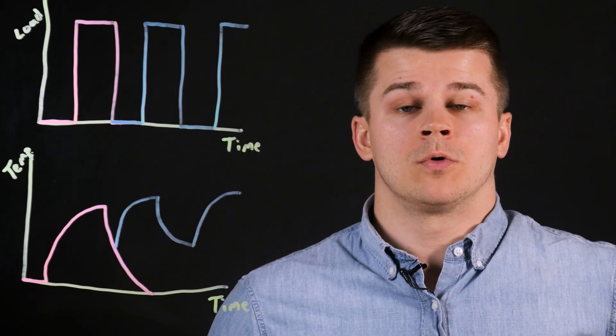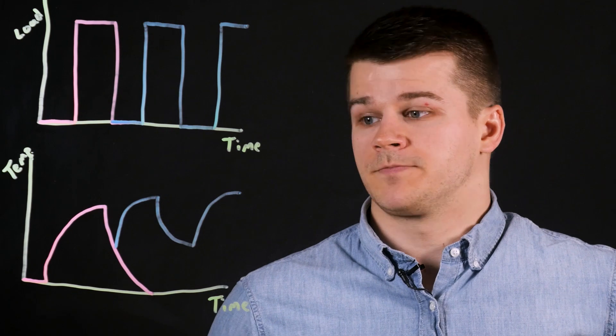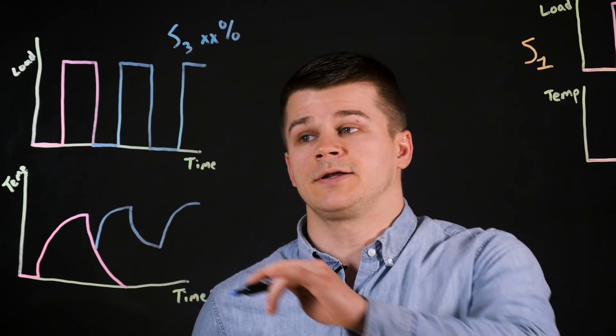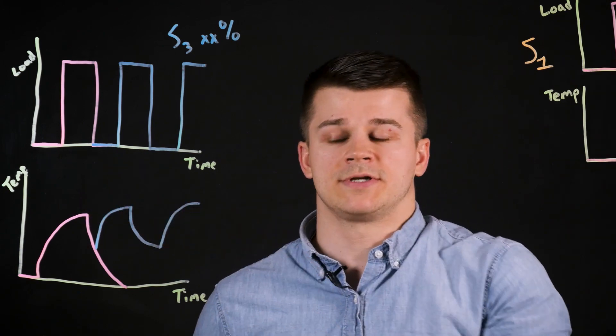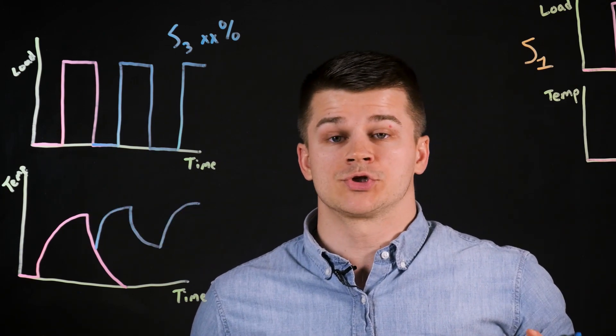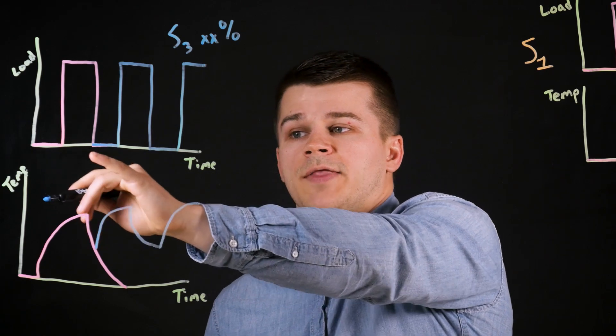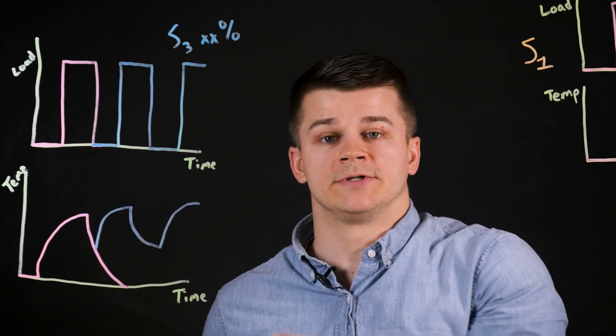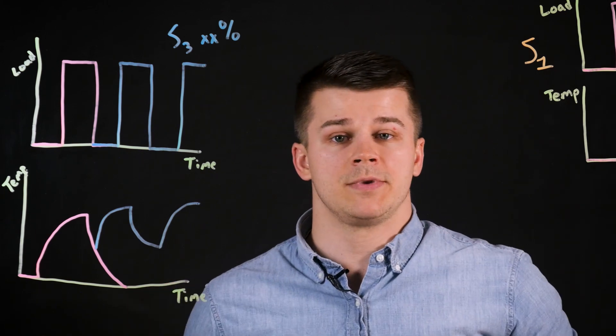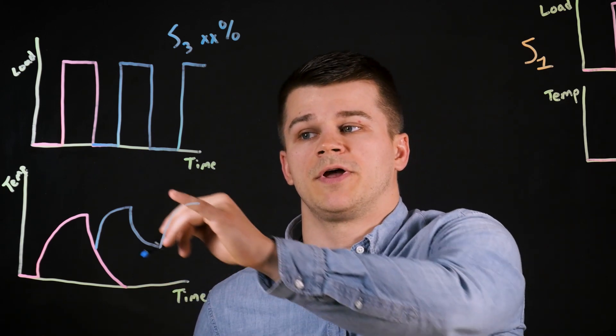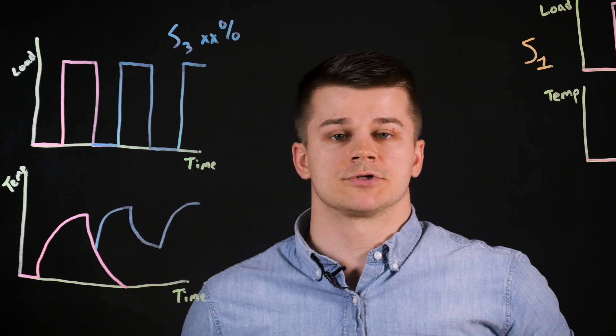This graph shows S3, or intermittent periodic duty. This type of duty cycle has identical cycles of a constant load followed by a period of rest, repeated over time. It's similar to short-term duty where the constant load is applied, and then when it's at rest, the motor is allowed to cool down. Unlike short-term duty, it's never allowed to reach the ambient temperature of the environment, but then the load is reapplied so the temperature spikes back up.